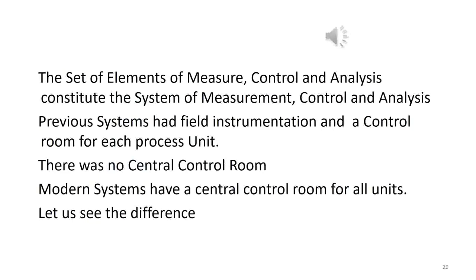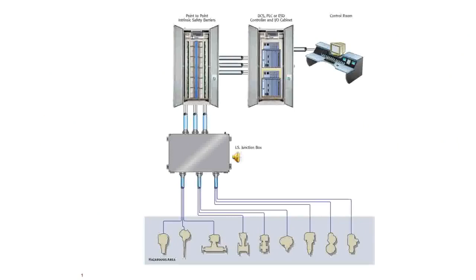The set of elements of measure, control, and analysis constitute the system of measurement, control, and analysis. Previous systems had field instrumentation and a control room for each process unit. There was no central control room. Modern systems have a central control room for all units. Let us see the difference. The classic and most used distributed control system is constituted of field instrumentation on the bottom of picture, junction boxes, multi-cables, and two cabinets, one with intrinsically safe isolators and the other with input-output modules and controllers, and workstations with monitors.